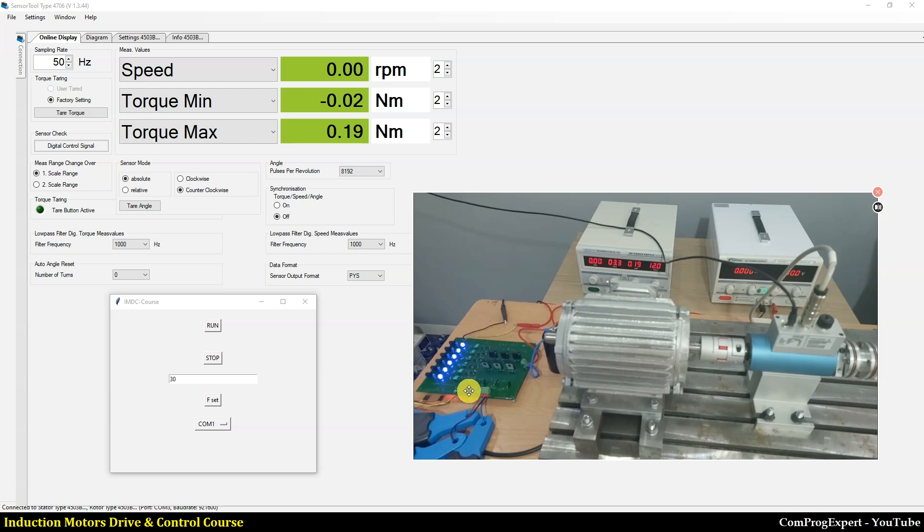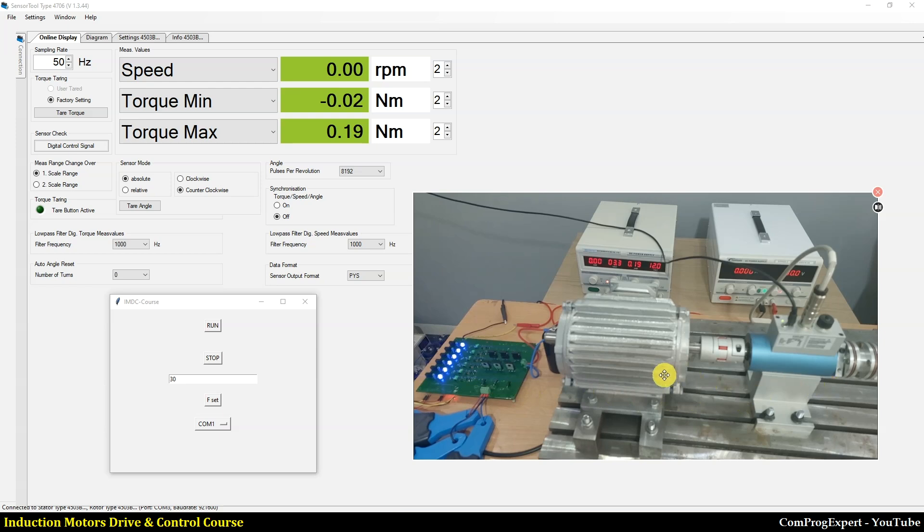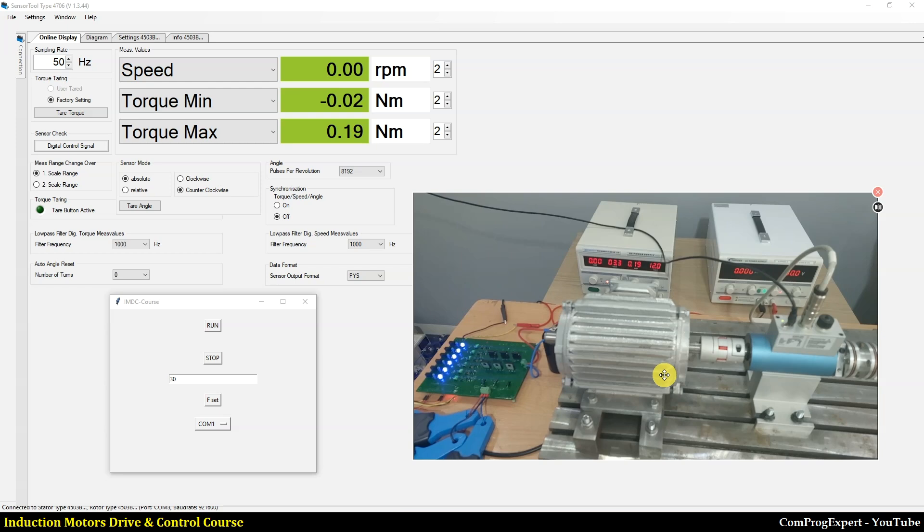In this test, we are going to check the developed code for VF control. Here I didn't attach the load to the motor and I'm just going to set the frequency of the rotating phasor in this test. We use SPWM method and in the next tests we will implement the space vector PWM.